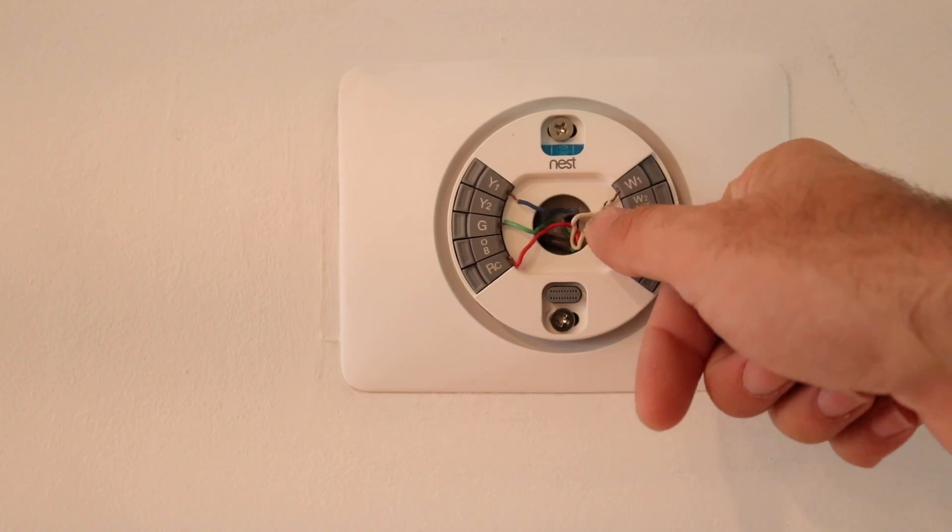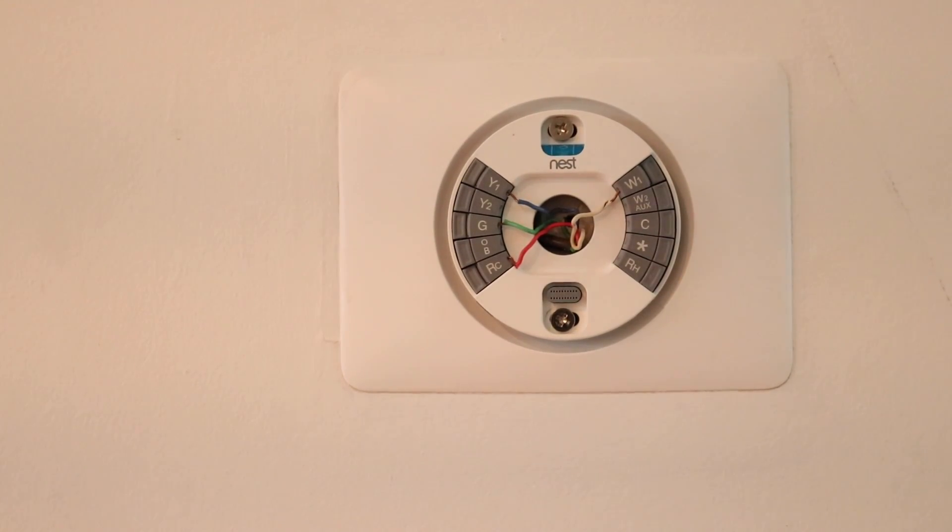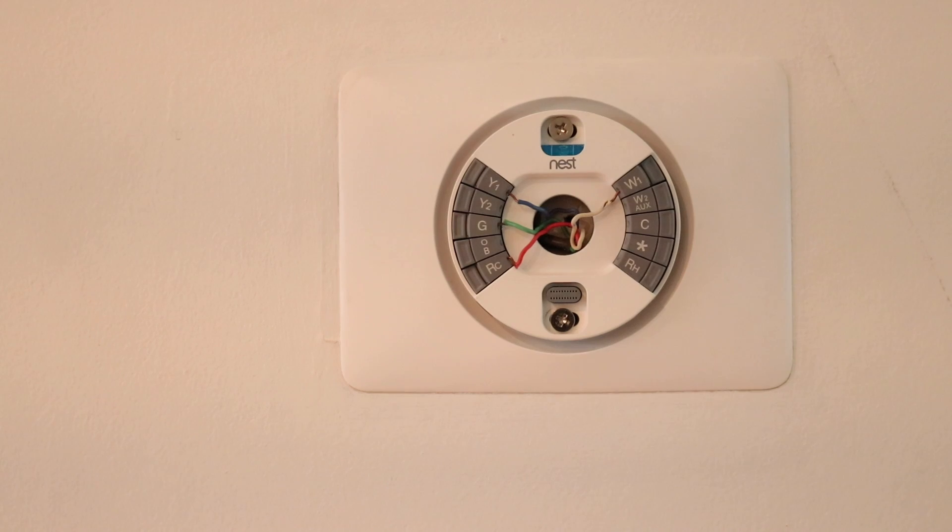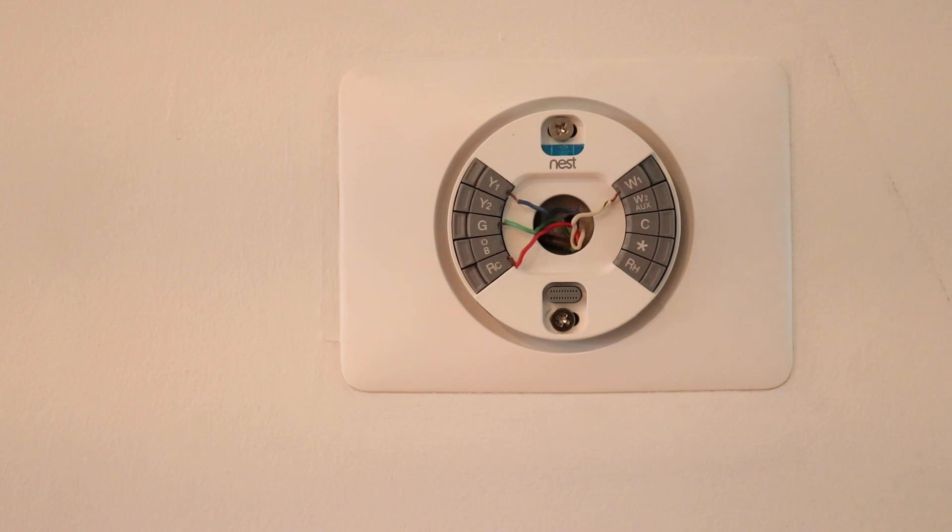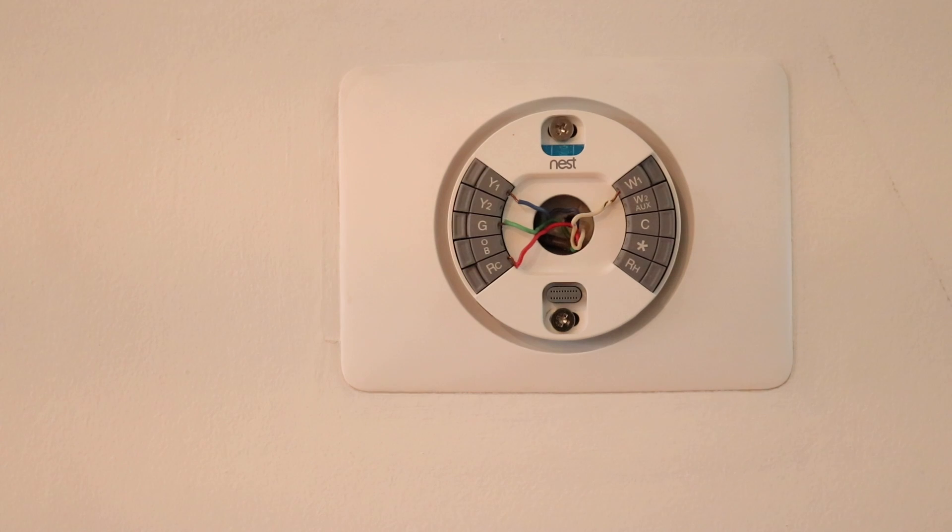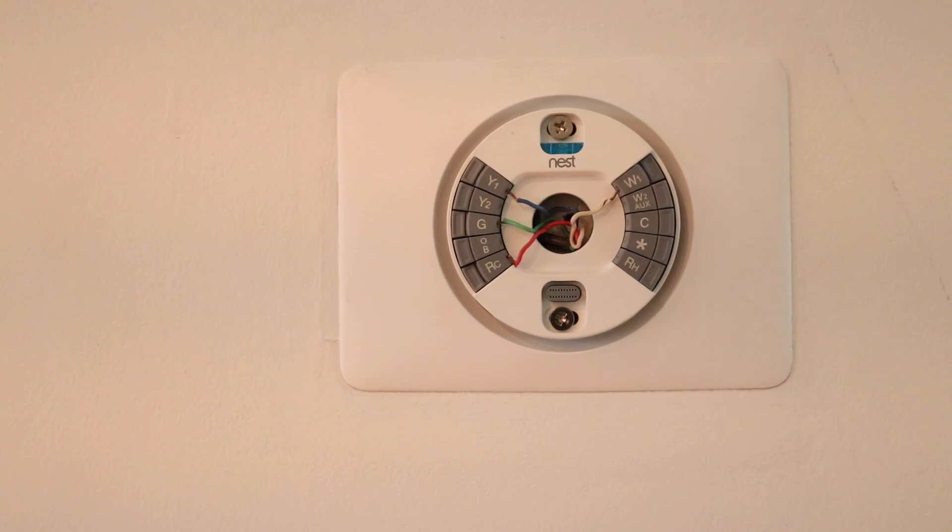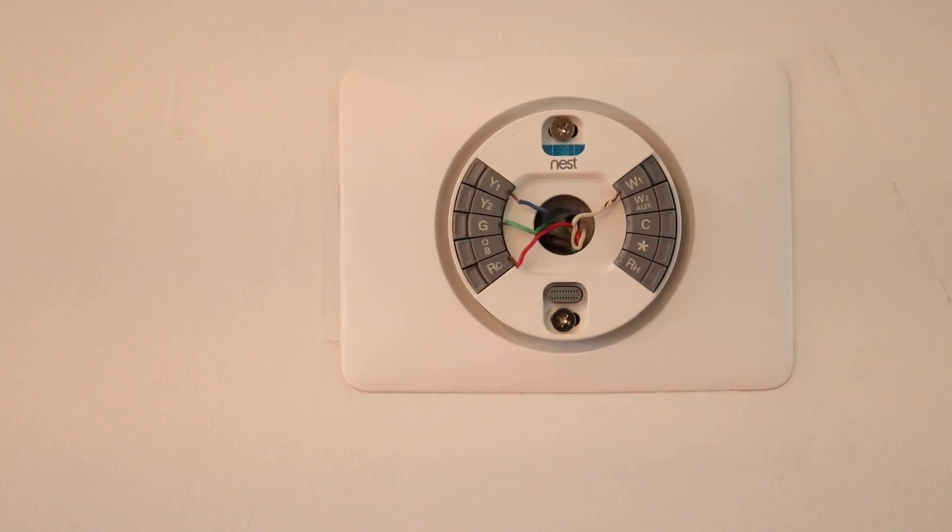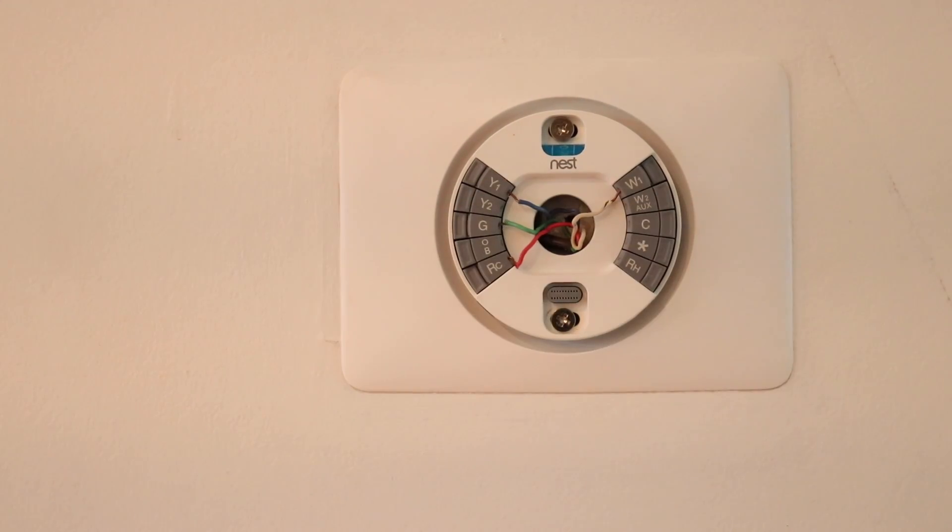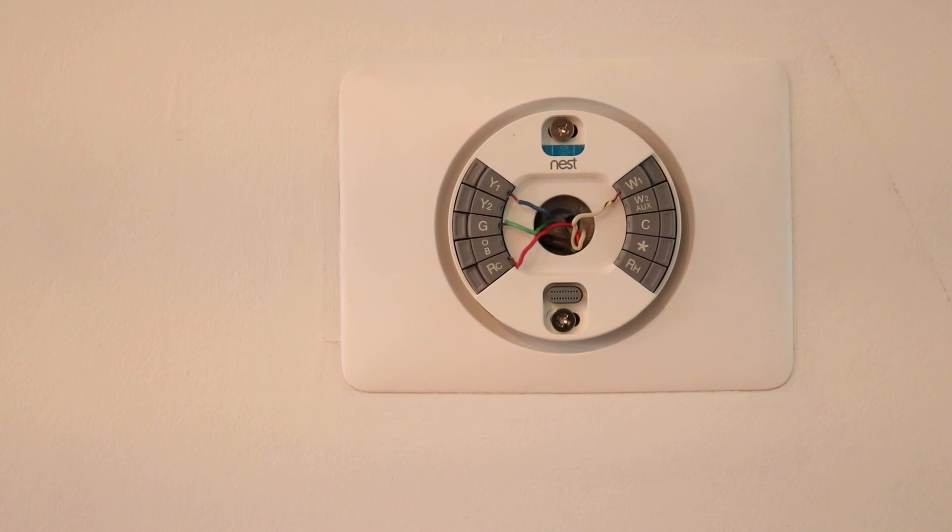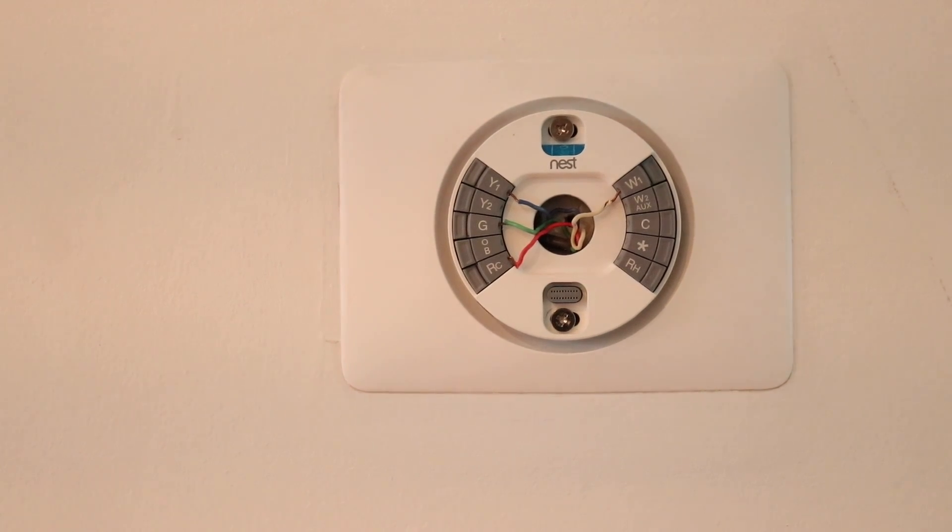So the white wire W1, that is your heating wire. That is the relay that goes to turn on your heat. The Y1, that is your cooling wire. That is the relay that goes to turn on your air conditioning. The RC or the RH, that is your power wire. And the G wire, that is your fan wire.